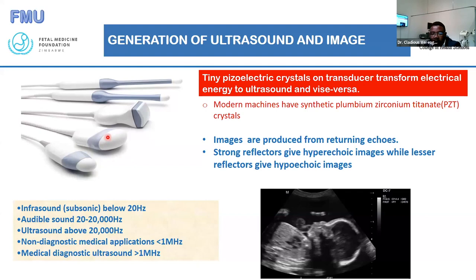They are curvilinear probes, used for abdominal scanning. What's important on this probe is to know that underneath the surface are what you call piezoelectrical crystals, arranged in a longitudinal fashion. So there are piezoelectrical crystals inside the probes. Modern ones are made of synthetic plumbium zirconium titanate, but they are arranged in the same way.